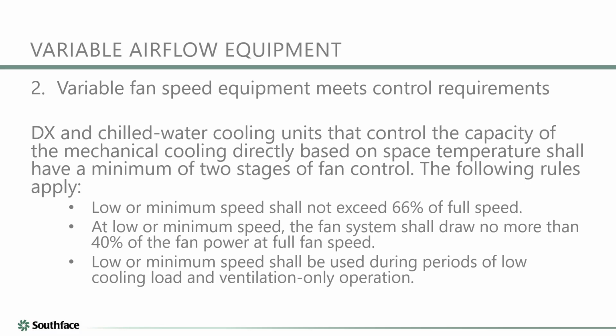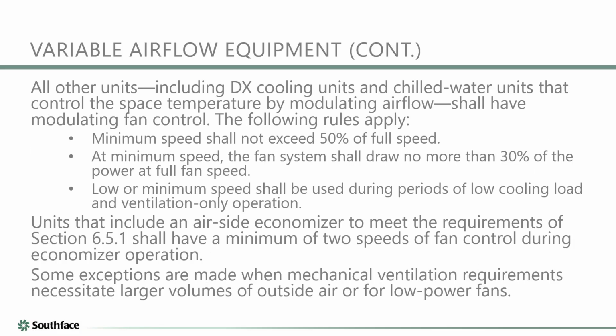Like we sometimes talk about, and I think we will in this presentation at some point, matching the ventilation load within a room. We're also looking to match the fan speed to the load that's on the equipment. In doing so, by being able to operate at essentially different phases, we're able to get greater efficiency out of the equipment. So variable speed equipment is a great thing in our energy efficiency, high performance mechanical system world. When you have it, it needs to meet these parameters so that you actually get the benefits of multiple speeds from the equipment. So there are our numbers for the chilled water cooling units, and then something that I think we'd probably see more here is DX cooling. The numbers are a little bit different, but the principles are the same. You want to make sure that your minimum speed is actually saving energy and drawing less power.